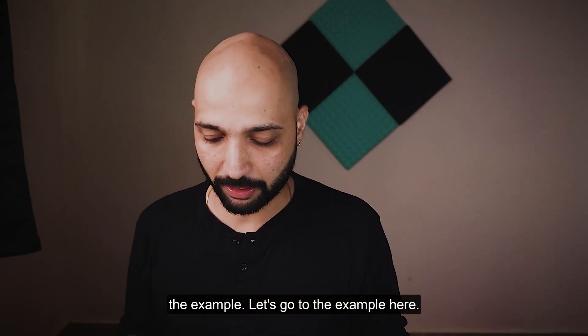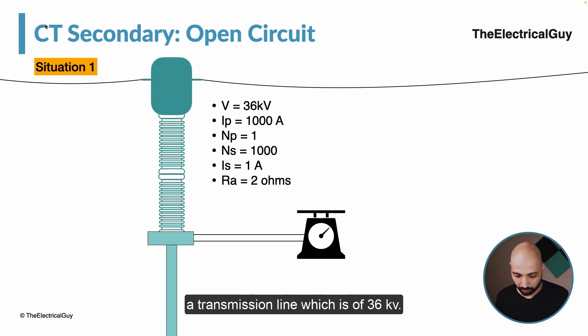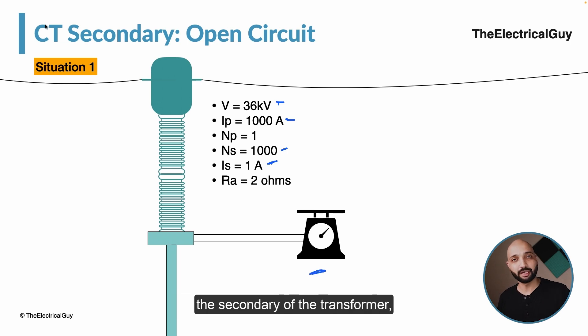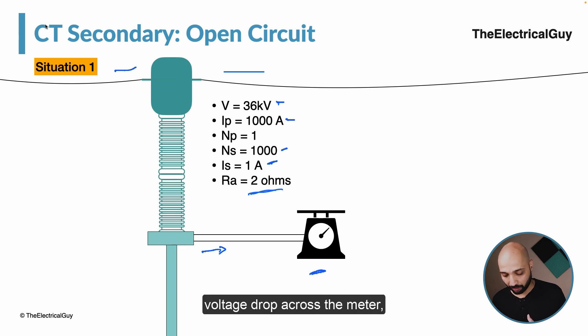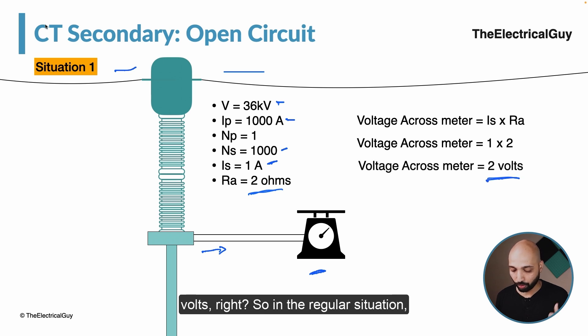Let's look at a numerical example. Situation one — a current transformer connected to a 36 kV transmission line. Primary current is 1000 A, primary turns is 1 (single turn), secondary turns is 1000, secondary current is 1 A, and the meter connected to the secondary has a resistance of 2 ohms. The voltage drop across the meter is simply secondary current times resistance: 1 A × 2 Ω = 2 volts. That is perfectly fine.